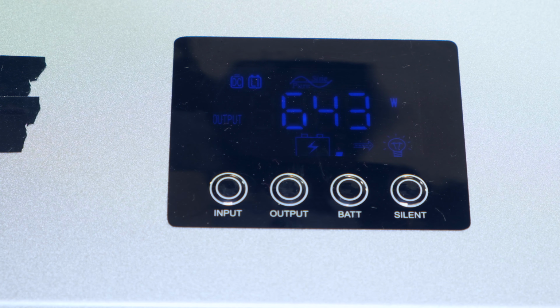And it does go about 10% above. There you can see 660, that's 10% full load. But that circuit breaker will only trip when there is a fault condition, if something is damaged. So it's not going to trip if somebody's overloaded it for a certain period of time, unless I wanted it to do that. If I wanted to protect the inverter from even someone going just even 10% over full load, well then I would have had to have made the circuit breaker a little bit lower in its current capacity.